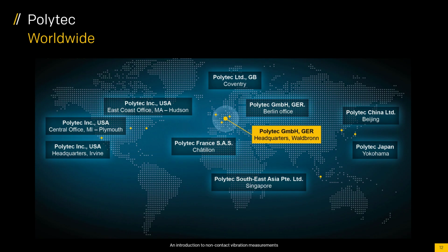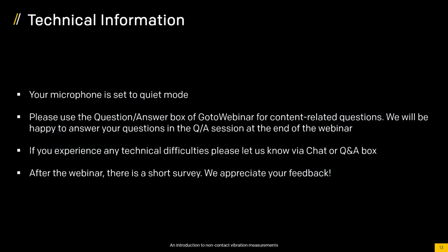Thank you, Vikram. The next question I have here is, can I use IQTec and HeNe with one set of electronics? So the new scanning LDVs, the VibroScan series, is actually an IQTec HeNe. Absolutely, all our VibroScan series, we have almost done the best of both worlds with that. In the past, the IQTec technology was applied only to IR, but everything is IQTec with the VibroScan now. So absolutely.